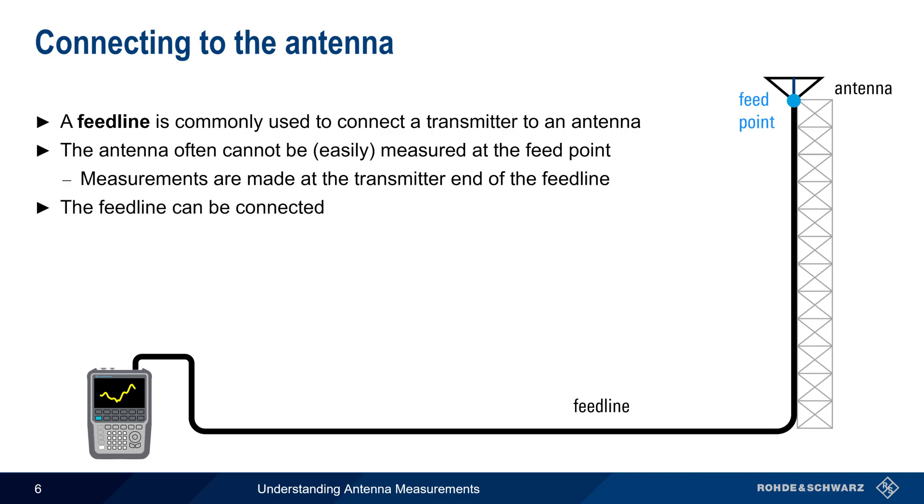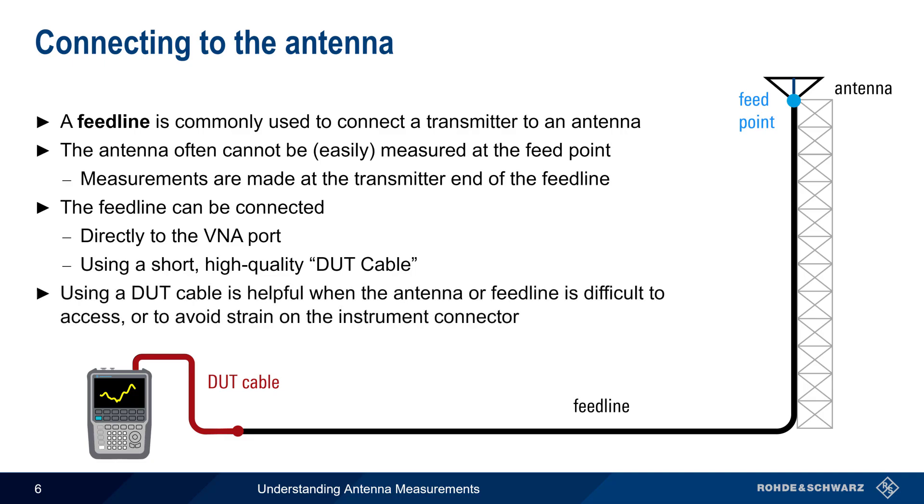There are two methods of connecting a feed line to a VNA. The first is simply connecting the feed line directly to the VNA port. The second is using a short, high-quality DUT or Device Under Test Cable. This is often done for ease of attachment, or to avoid strain on the instrument connector.